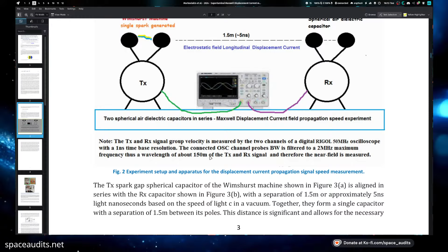The connected OSC channels probes BW is filtered to 2 megahertz maximum frequency. Thus, the wavelength is about 150 meters of the transmitter and the receiver signal, and therefore the near field is measured. BW is bandwidth. Thank you.